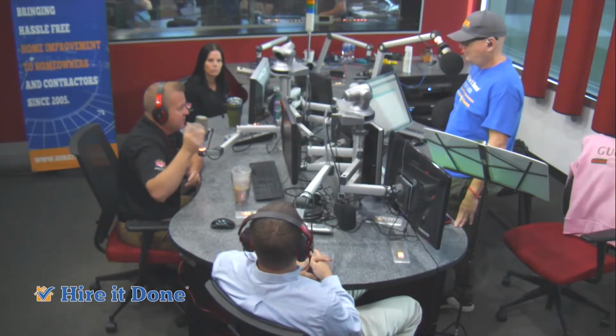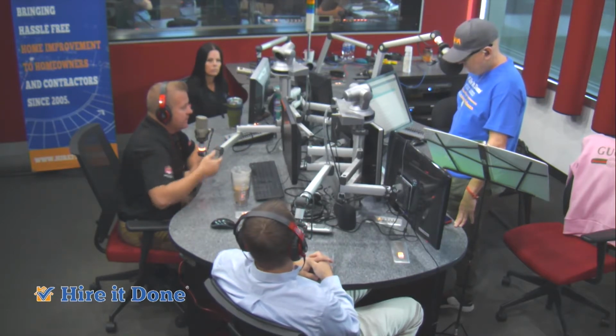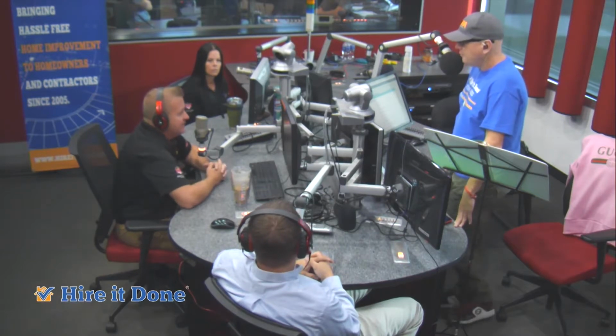We see this a lot where they put new insulation in there. It's R49. They have the baffles. Everything's great. And then you walk in the house and you see a whole house fan. You're like, whoa, what's going on here? They can't figure out why the roof's ice damming. Well, you're just dumping all this heat. They crank it up, so it's like 80 degrees in their house, and then all that heat is hitting that whole house fan going right to the attic. So, yeah, it's a complete system, and that's why we do complete system selling.